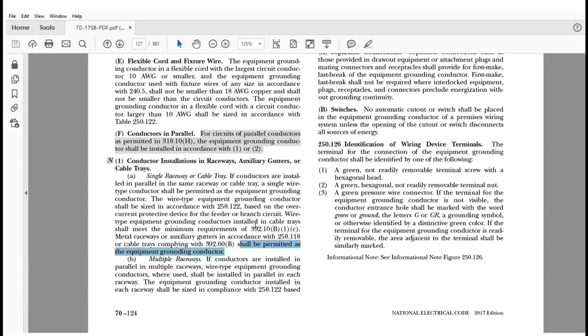However, the code is saying, look, we're also going to recognize that the raceway, the cable tray, or the auxiliary gutter, as specified in 250.118, or if it's a listed product like in 392.60(B), then we're going to let you use that as the equipment grounding conductor when we're dealing with the paralleling of a single raceway or cable tray for this application where you have parallel conductors run in it. We're going to let you do that, and that is pretty consistent. We don't have an issue with that, as long as it qualifies under 250.118.